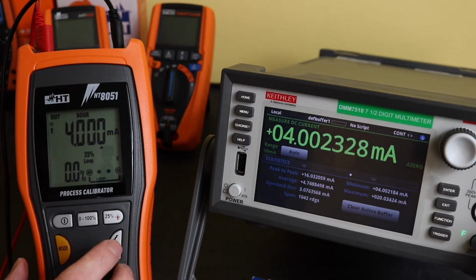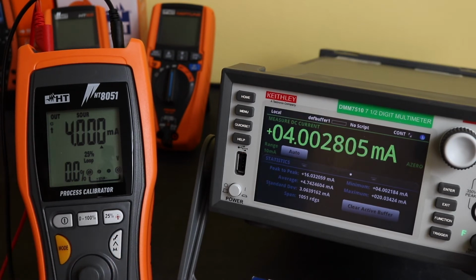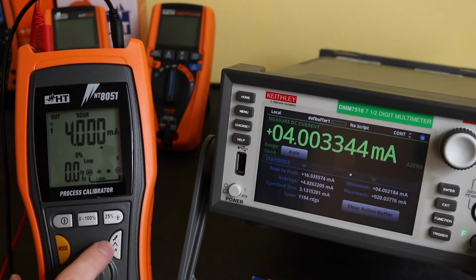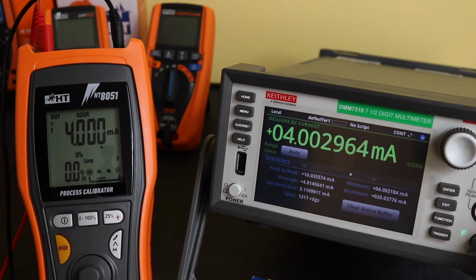This next button down here is for ramp modes, and this has 3 different ramps available. The top one here, the stepped one, will take it from 0 to 100% and again back down to 0 in 25% steps every 5 seconds. The second one, which is the large triangle, is a slow linear ramp which is 0 to 100% and back down to 0% in 40 seconds. And then the very bottom one here is a fast linear ramp, which again is 0 to 100% back down to 0 again in 15 seconds.